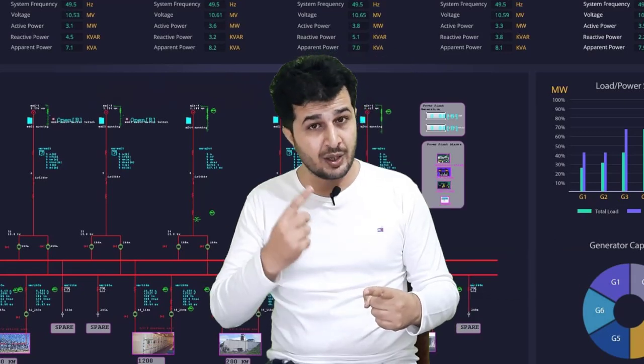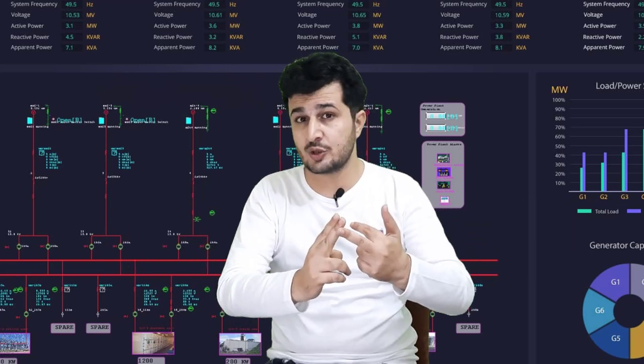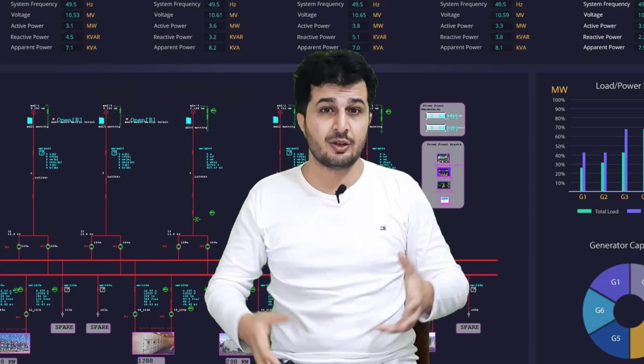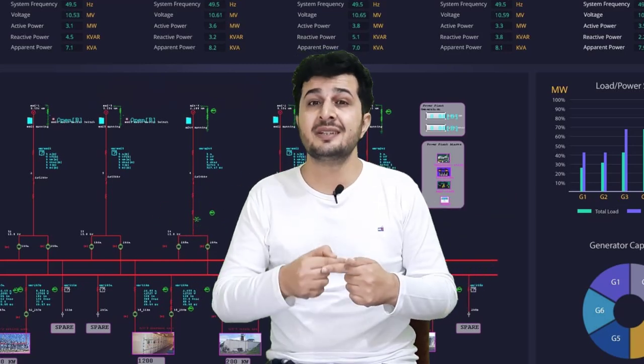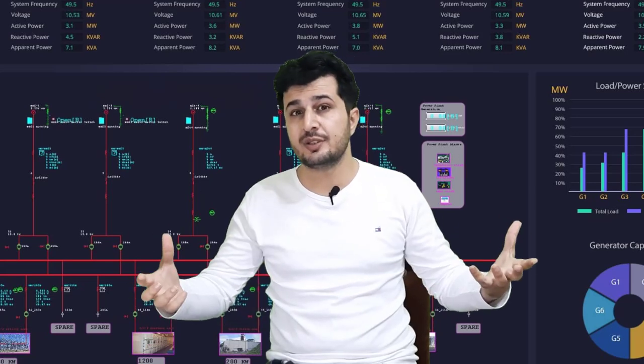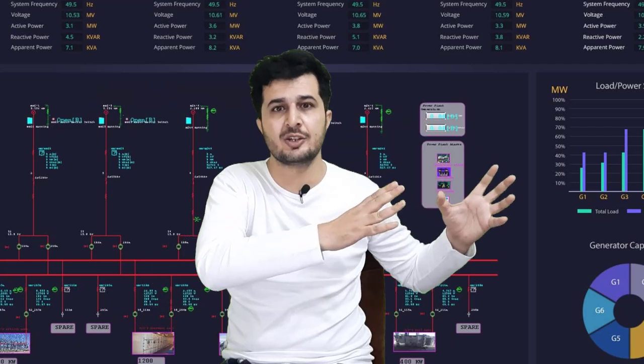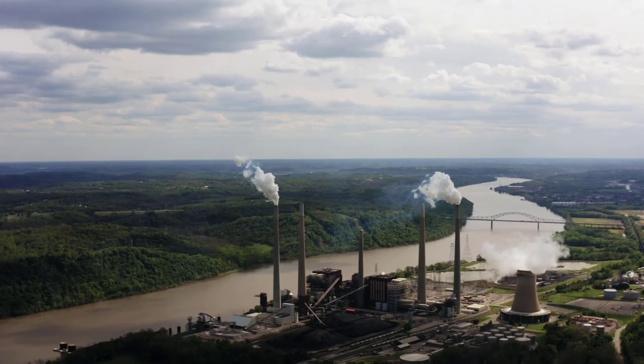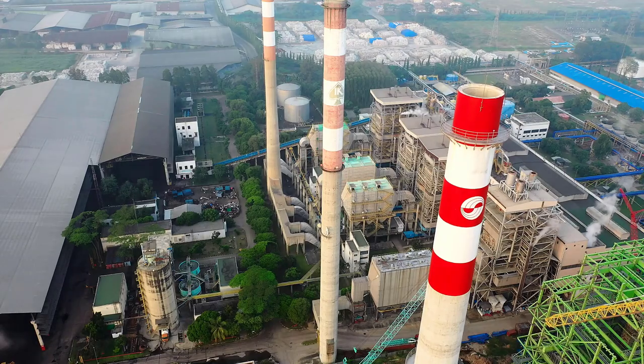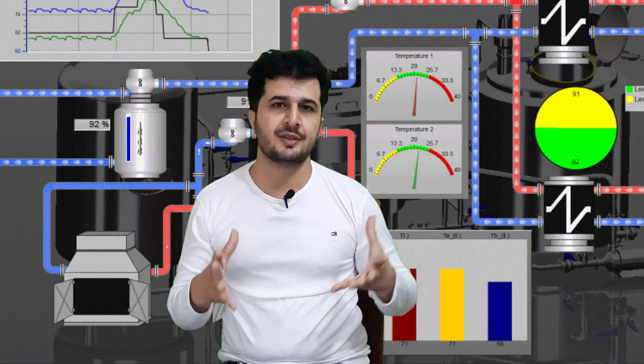If one area controller in a DCS system fails, it is not going to affect other areas. If one controller fails in a single area, there is also a redundant controller present. In the case of failure of the main controller, the redundant controller will take over the job. That's the beauty of the DCS system — your process is controlled by different controllers, not one single controller. If it is a larger system and you need historical data, then you should opt for a DCS system.